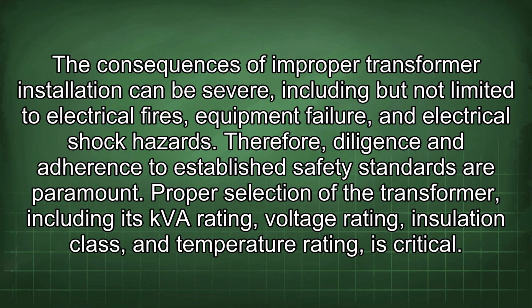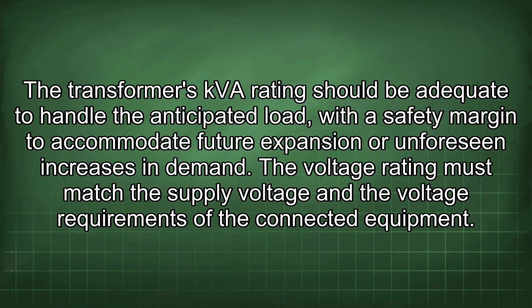The consequences of improper transformer installation can be severe, including but not limited to electrical fires, equipment failure, and electrical shock hazards. Therefore, diligence and adherence to established safety standards are paramount. Proper selection of the transformer, including its kVA rating, voltage rating, insulation class, and temperature rating, is critical. The transformer's kVA rating should be adequate to handle the anticipated load, with a safety margin to accommodate future expansion or unforeseen increases in demand.